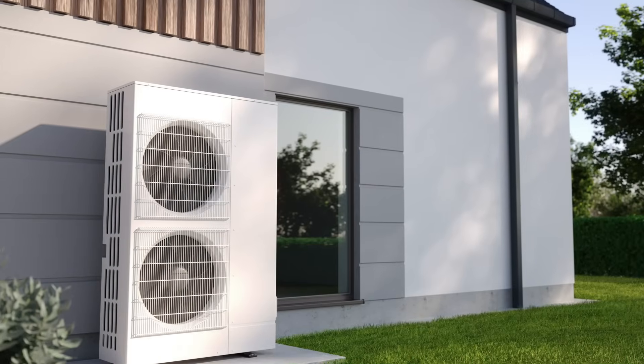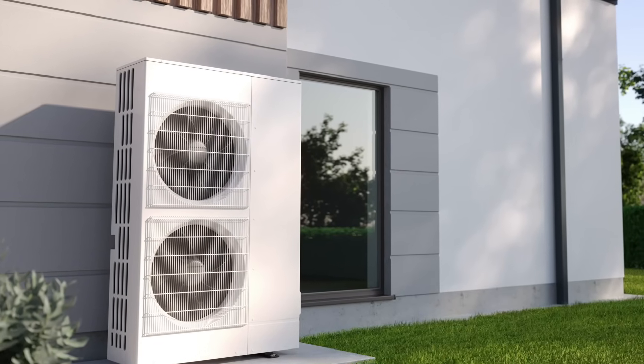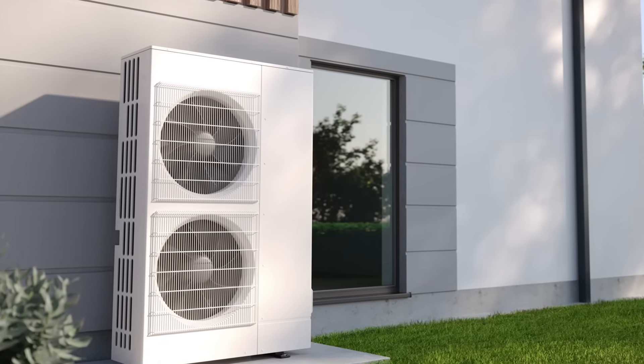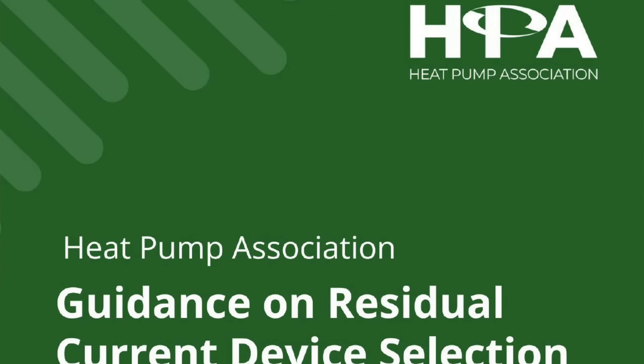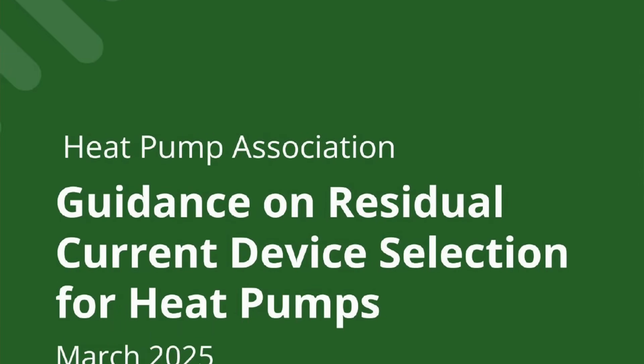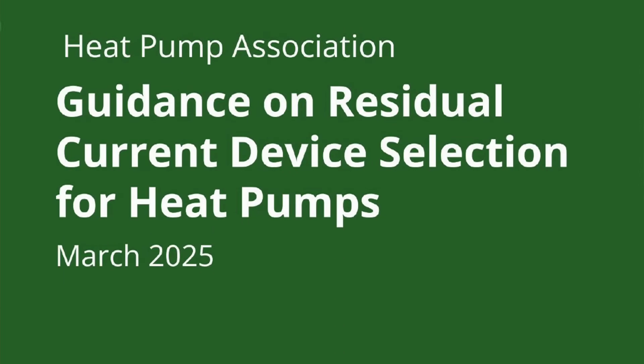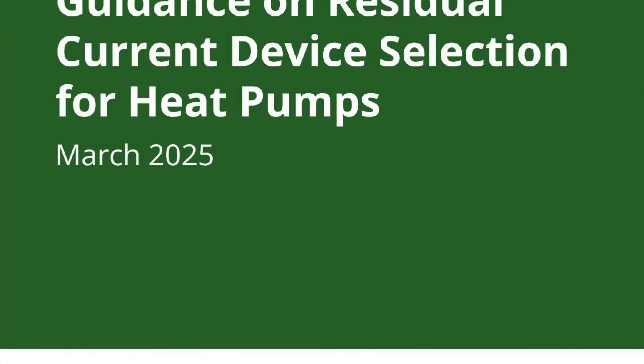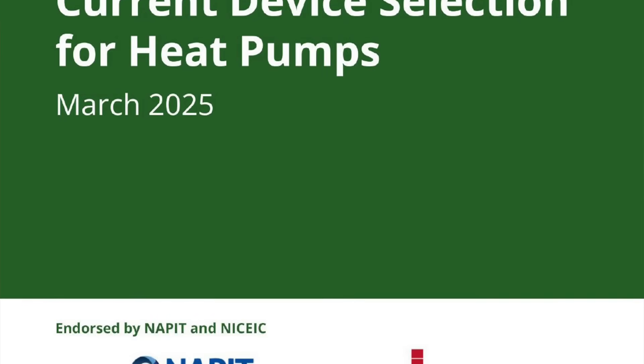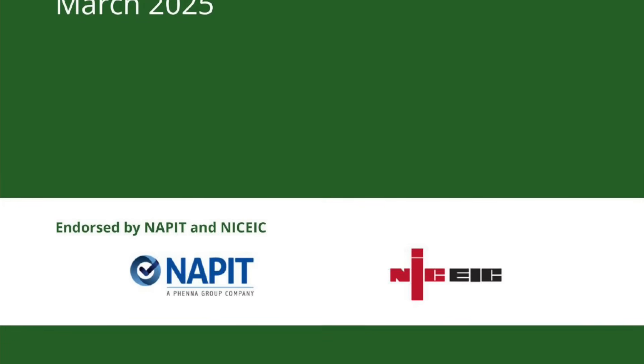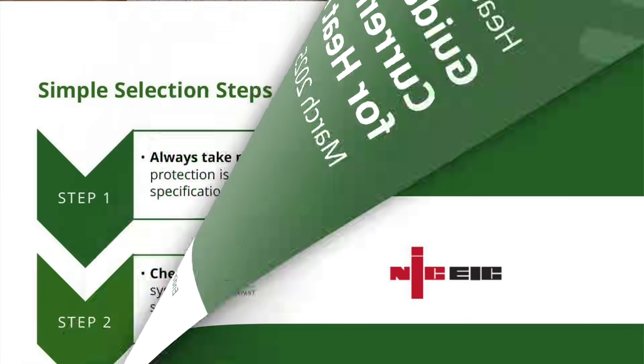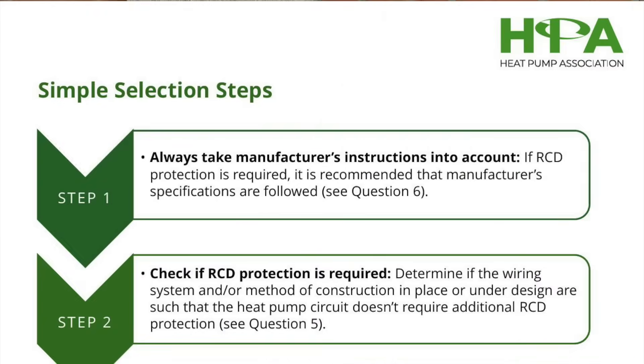Selecting the correct RCD type isn't just about meeting regulations — it's about ensuring your installation functions smoothly without unnecessary tripping or safety risks. To help you select the correct RCD, the Heat Pump Association have produced a document called the Guidance on Residual Current Device Selection for Heat Pumps, made in association with NAPIT and the NICEIC. In that document, we find an easy-to-follow four-step process to get the right device.